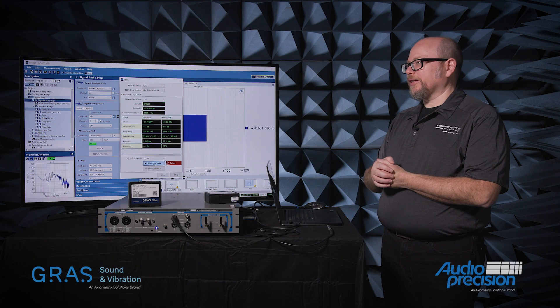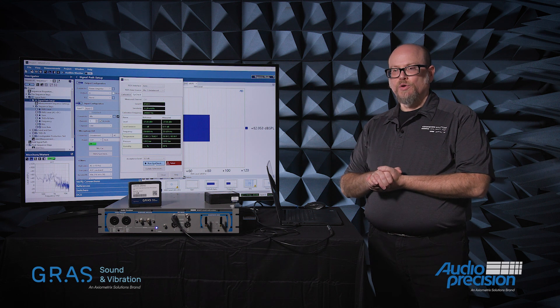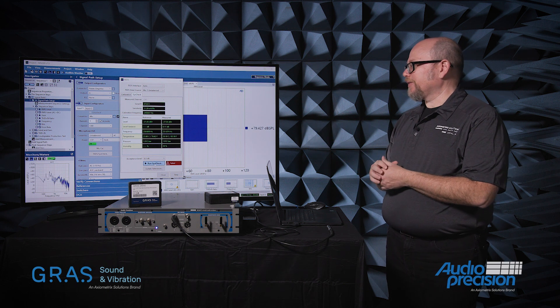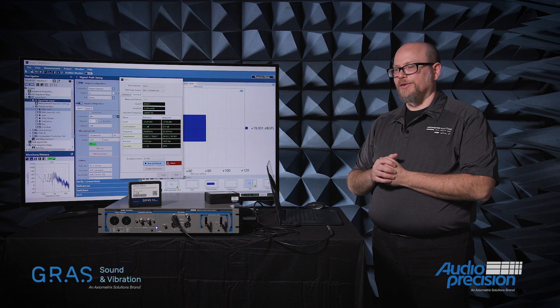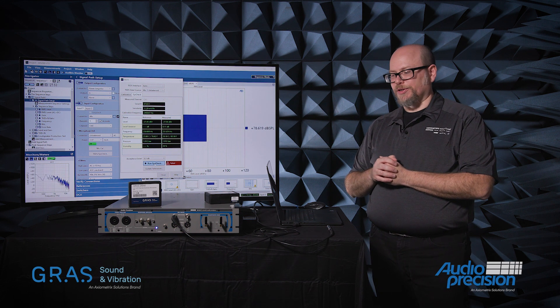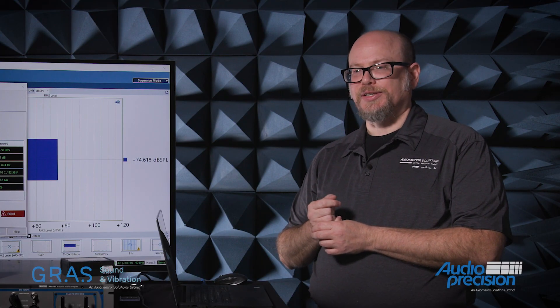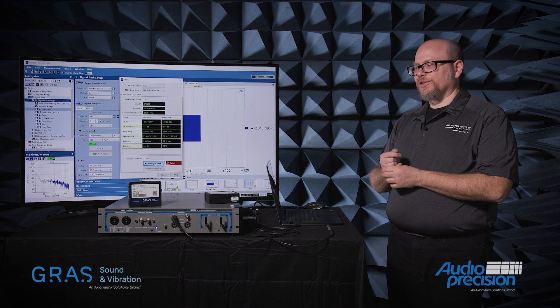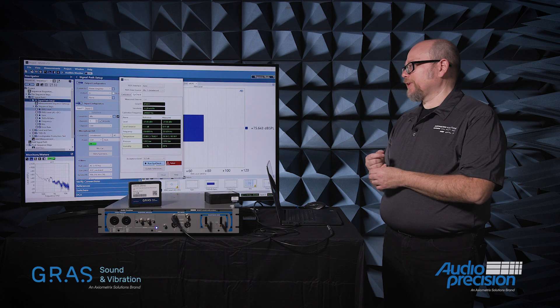In this case, I decided that the default acceptance level would be 0.3 dB. Now, it has failed. What the system has done is measure the value of the reference signal generator, compensated for the ambient temperature — there are actually temperature, humidity, and static pressure sensors embedded in this microphone as well — and algorithmically determined that we are not within 0.3 dB accuracy.